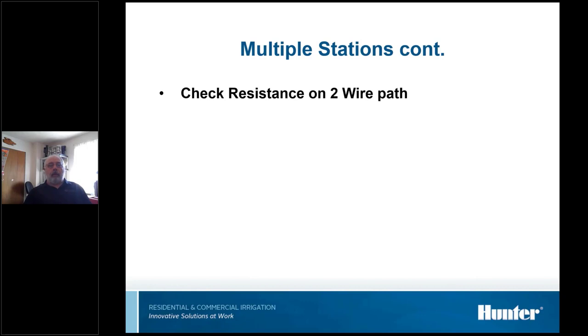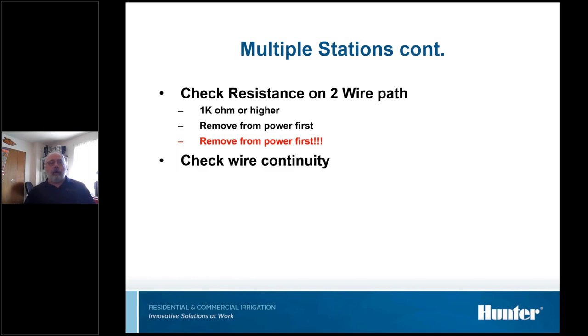Then once you get to that point, we're going to check resistance on the two wire path. Again, like I say, I don't use resistance of the two wire path as much of an indicator. It should be higher than 1K ohm. It should be a lot higher than that. But I've seen readings down that low and everything was okay. Like I say, if you're checking resistance, turn the power off first.